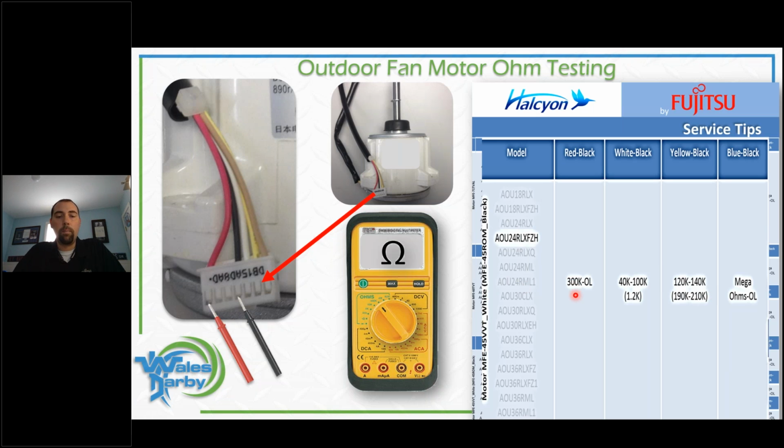But if I have an auto ranging meter that's going to kind of do its own thing, it might actually move and give me a decimal reading. And that's where, if you're not understanding of what that decimal means, it might go to a mega scale, right? So it might auto range to a mega scale. So I might read it as 0.3 something, let's say 350,000 ohms. I might see 0.350. When I talk to tech support, the answer is not 0.350.